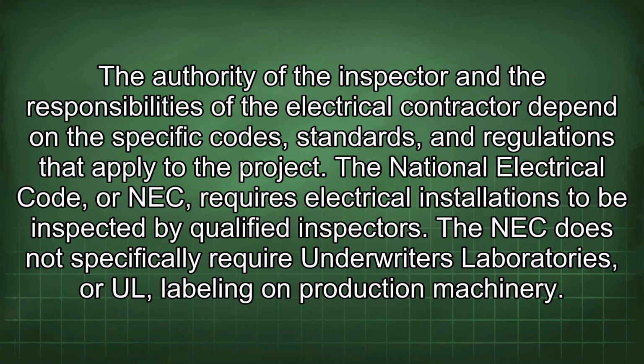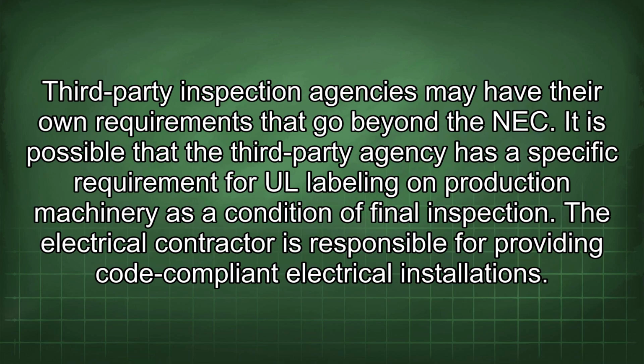The authority of the inspector and the responsibilities of the electrical contractor depend on the specific codes, standards, and regulations that apply to the project. The National Electrical Code, or NEC, requires electrical installations to be inspected by qualified inspectors. The NEC does not specifically require Underwriters Laboratories or UL labeling on production machinery. Third-party inspection agencies may have their own requirements that go beyond the NEC.